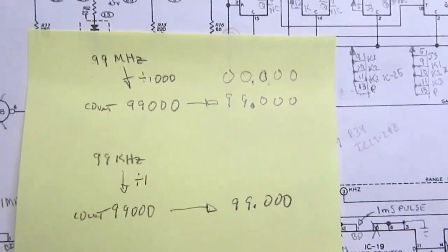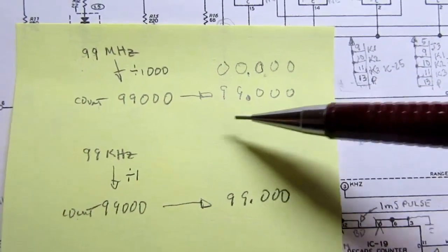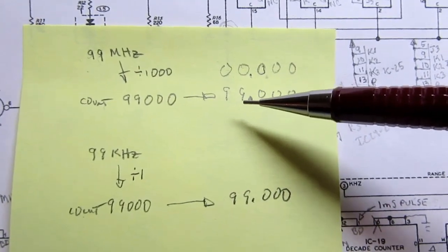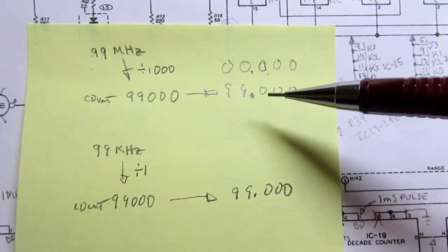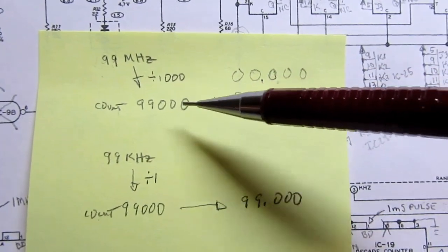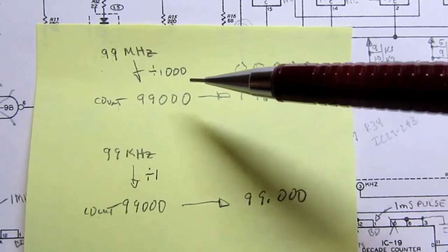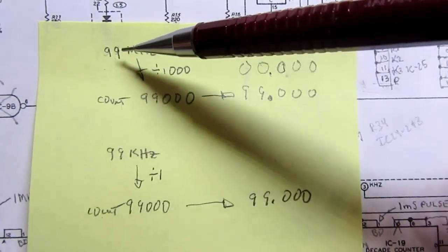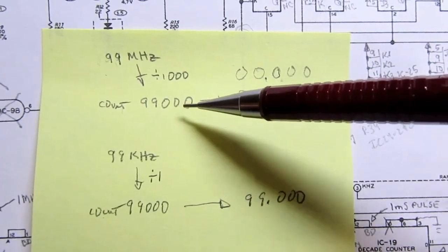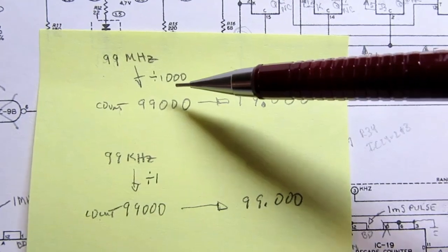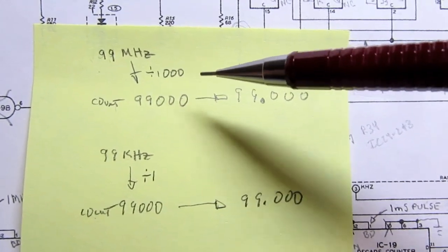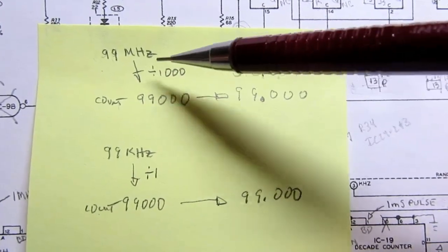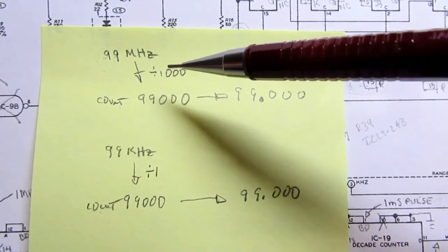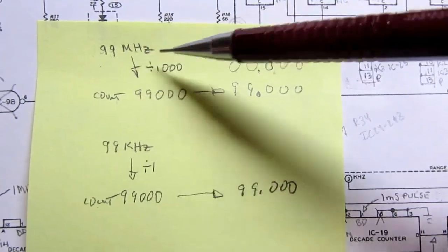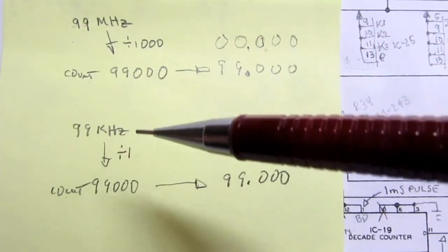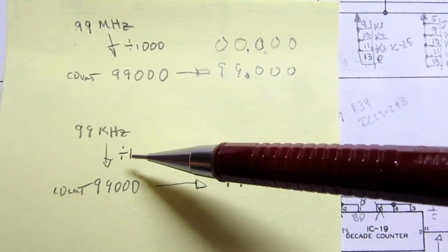Now what about megahertz? The display isn't any different, the counter isn't any different. It can still display 99.999 actually as its maximum count, but here I've got it written as 99000, so a little bit less than the full count. If you're going to come in with megahertz and expect it to count up to that, you need to count for 1,000th of a second, or 1 millisecond. So you need a gate of 1 millisecond duration, or a gate with a period of 1 millisecond, to be in the megahertz range, or megahertz mode more correctly. And in the kilohertz mode you need the 1 second long gate.